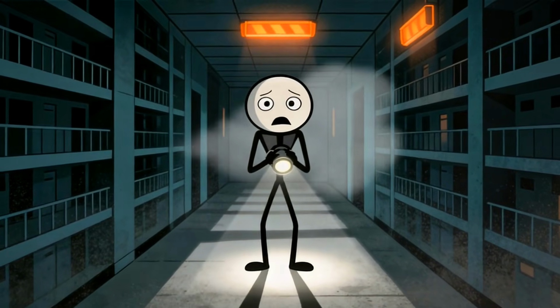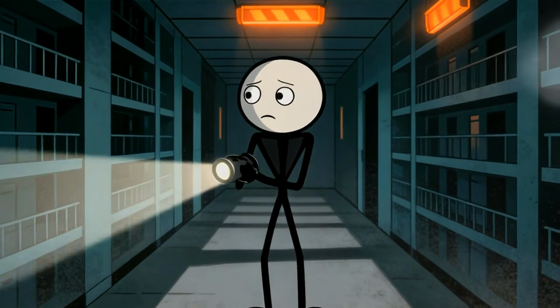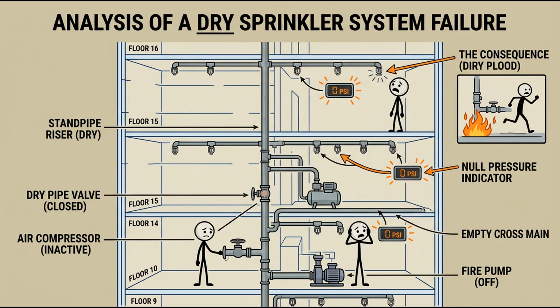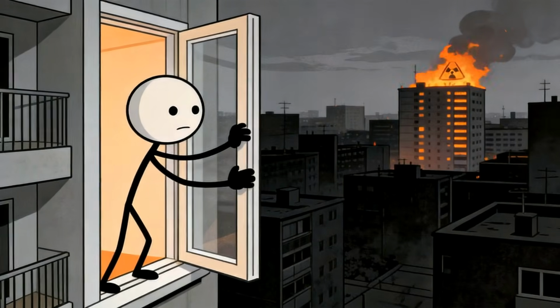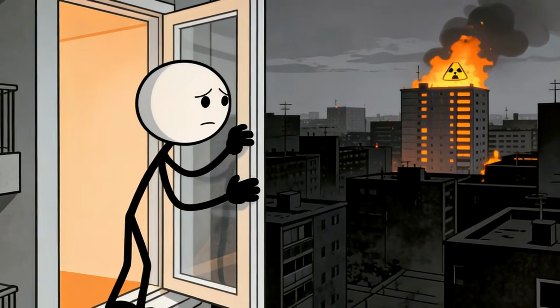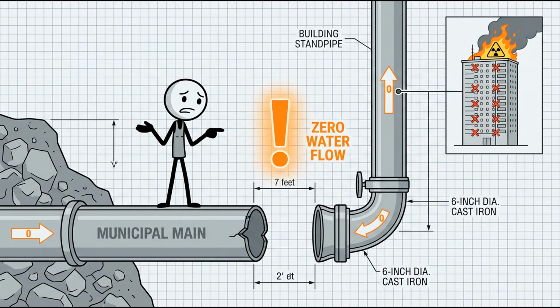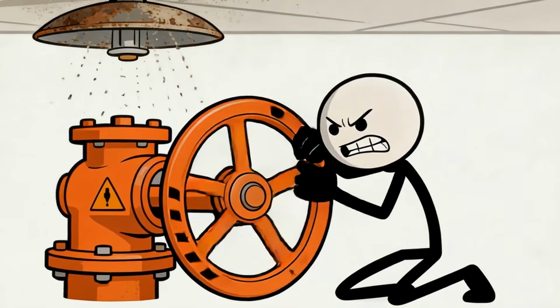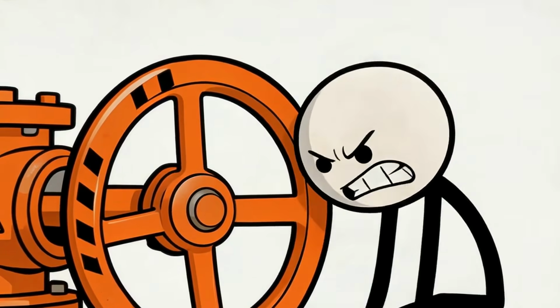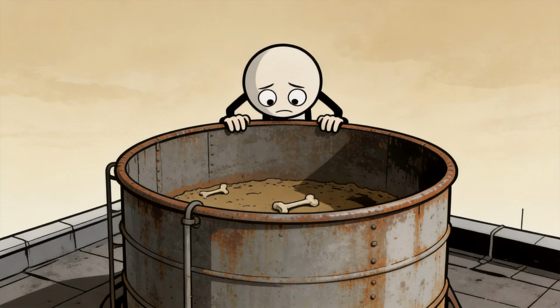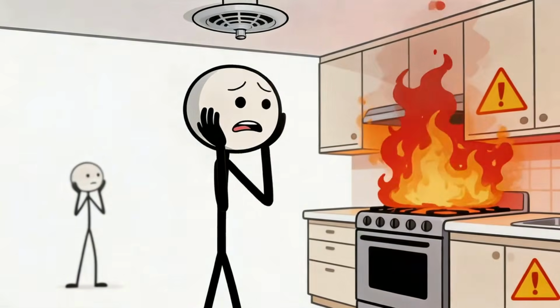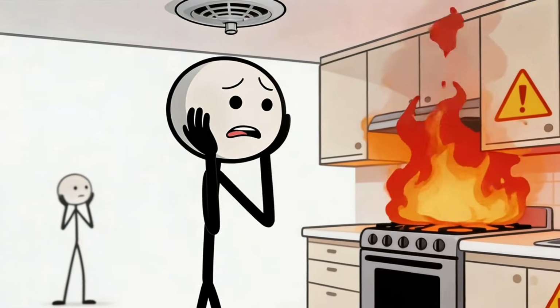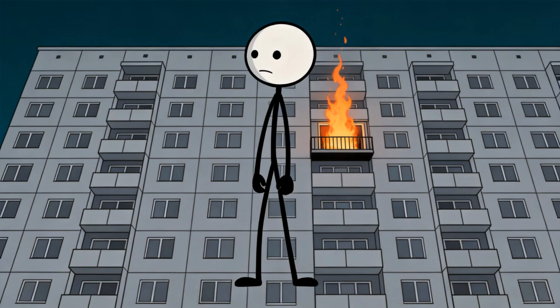But the most terrifying physical threat in a grid-down high-rise is fire propagation under null pressure. When the municipal grid is down, urban fire behaviour changes drastically. Without municipal water pressure, the standpipes and sprinkler systems in buildings over 10 stories are absolutely useless once the gravity rooftop tanks are drained. If a fire starts on day 3, there is no automated suppression to stop it.